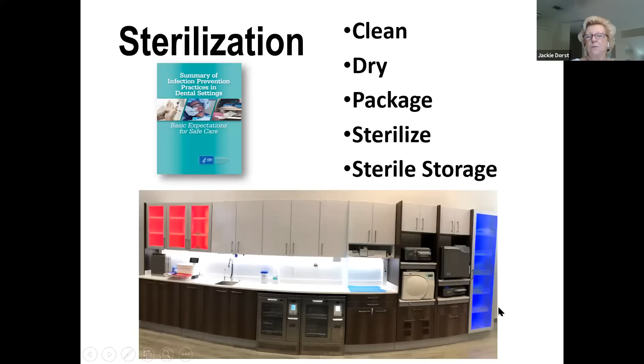Then the wrapped instruments will be sterilized. And once they're removed, they go into an enclosed cabinet for sterile storage to prevent contamination of the exterior of the package. It doesn't have to be that large of a sterilization room that you saw on the previous slide. Maybe your sterilization room's more compact, such as this one, that has an instrument washer and then a very small ultrasonic for just a few small items.